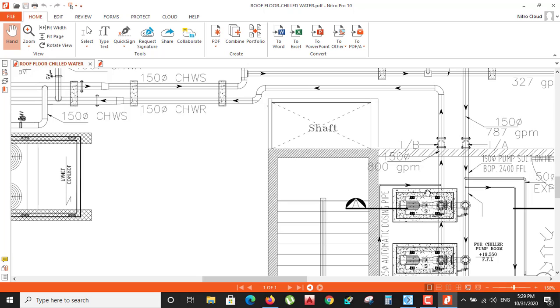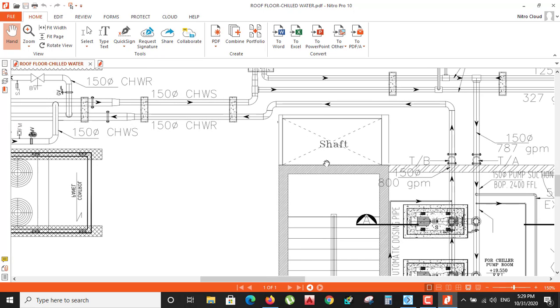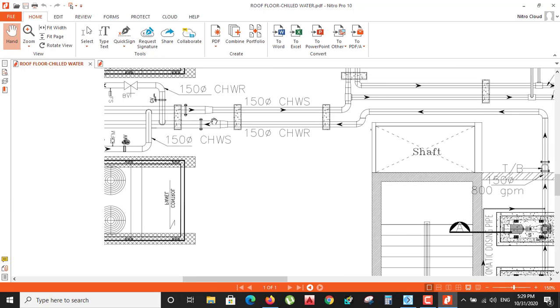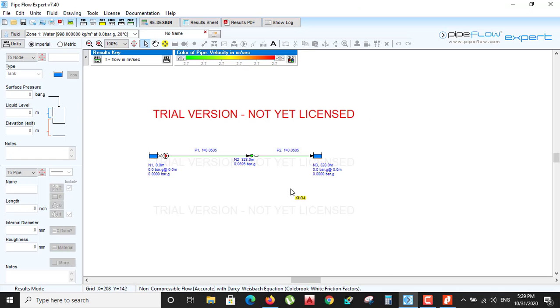So it was just an example of a pump, elbow, and its length. I just assumed the length. The lengths are not actual, so you can put in the actual lengths of pipe, actual fittings, and the other things, and use the simple equation: gallons per minute multiplied by head in feet multiplied by 1, that is specific gravity, divided by 3960. So this is the total calculation of this pump.